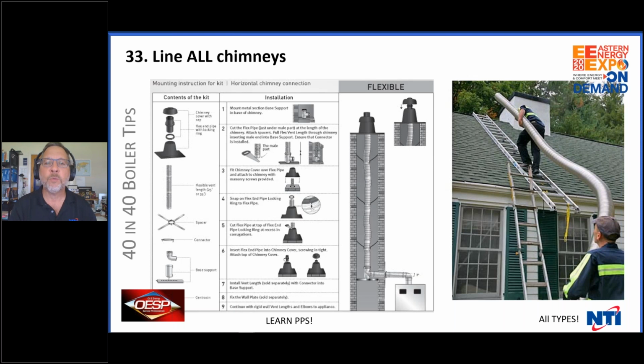Well, I can tell you this, there's a reason why on a gas atmospheric boiler, there's rollout switches. It's because we never clean chimneys. And there's so much condensation happening in that chimney, no matter where it is, that all the wonderful sheets of masonry are dropping down in front of the flue, which is causing products of combustion coming back in the house, which is why there's rollout switches. Yeah, line your chimneys. They make them in kits, in lengths, in diameter, and they even make them in polypropylene, flexible, in a roll for modulating condensing boilers. How lovely is that? Line your chimneys. Buy the kit, do it.